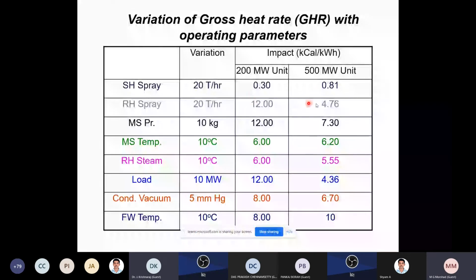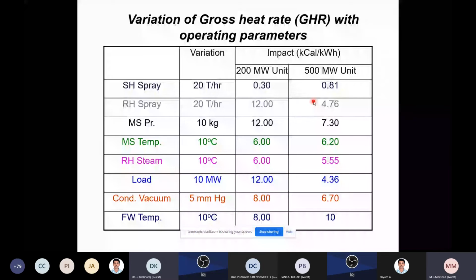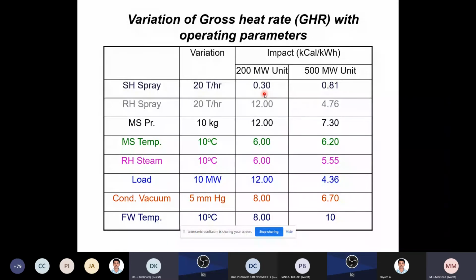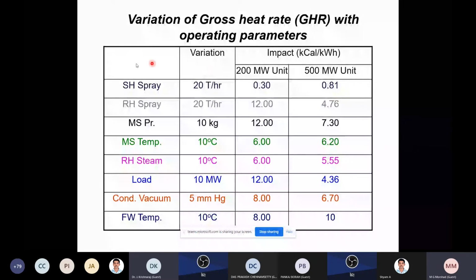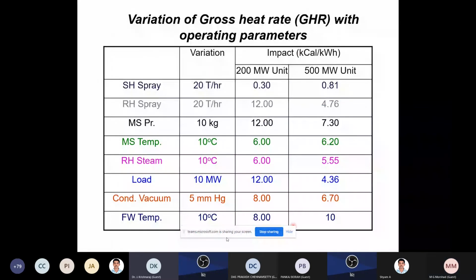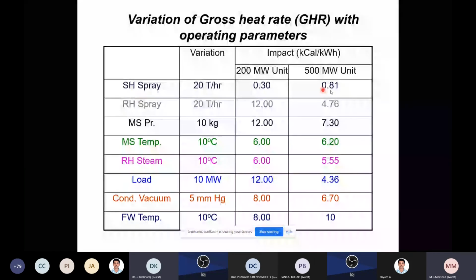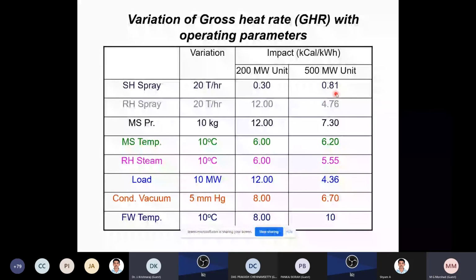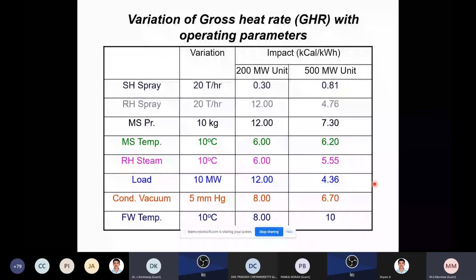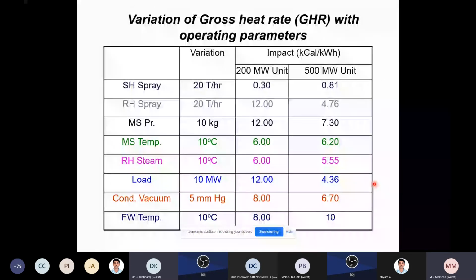I told you the gross heat rate is one of the very important parameters in an energy audit. The deviation of the gross heat rate has already been established by the BEE, and it can be verified with this data set and what you get from the local readings. You have to verify so that it will be somewhat accurate.